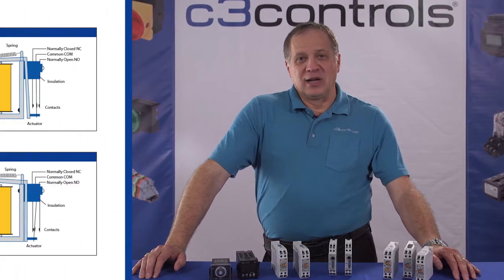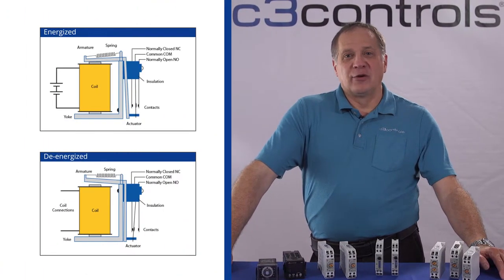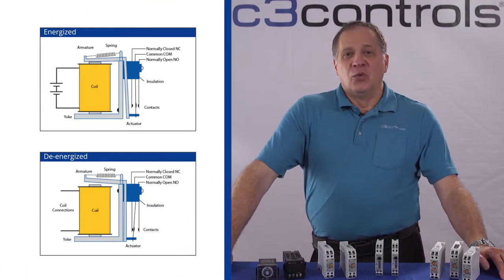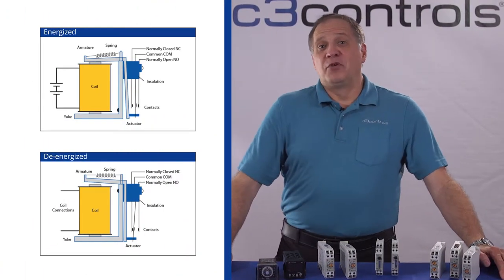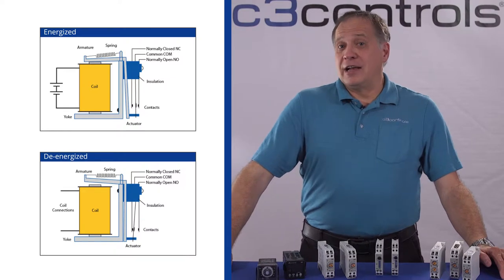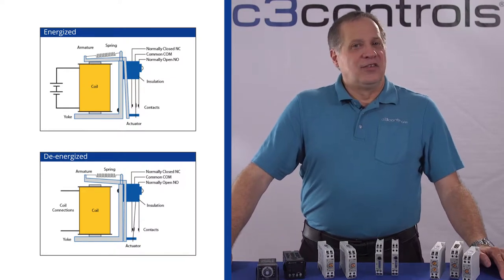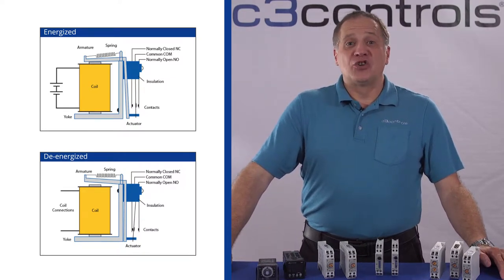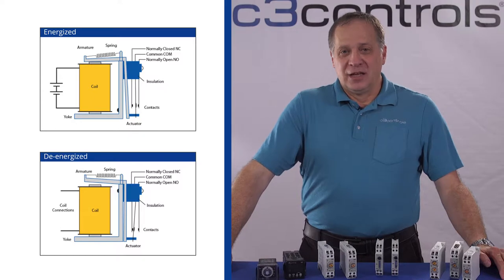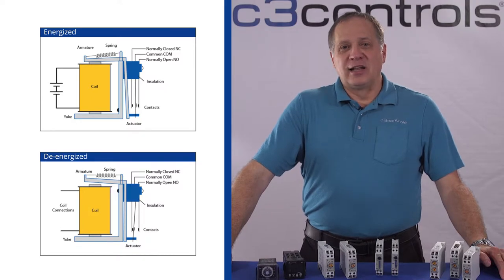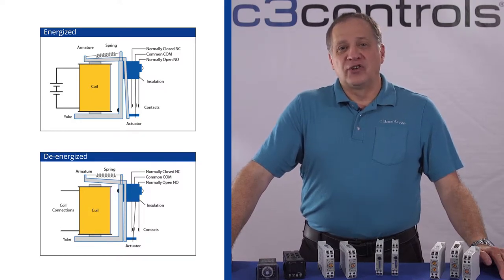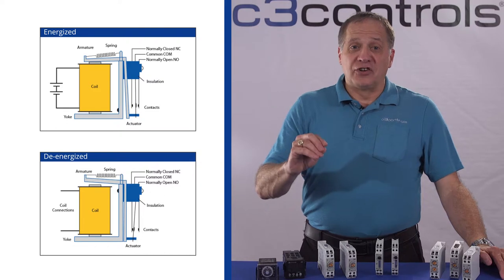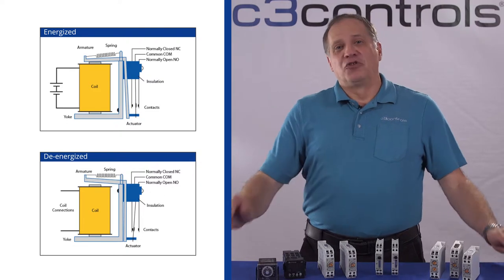An electronic timing relay has circuitry integrated into it which controls the armature motion when input voltage is applied. This addition gives the relay the property of time delayed actuation. Electronic timing relays are constructed to delay armature motion when the coil is energized, de-energized, or both.